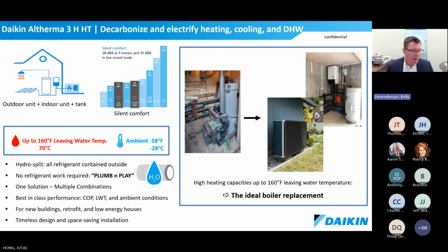Again, one solution will provide the heating, space cooling, and also serve the domestic hot water with a tank. And I'll show you more about how that works. And then we also see this as a high COP. We have outdoor reset, similar to what you'd see in a boiler, only it's a little bit more sophisticated, because we can match the load line of the envelope or the occupied space with the performance of the unit and the weather conditions, and we can strike the most economical balance on water temperature. Next slide, please.